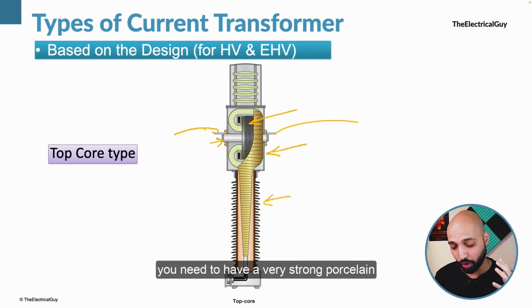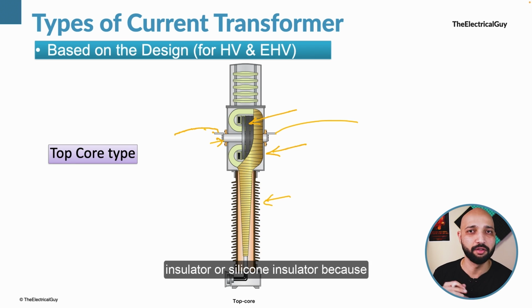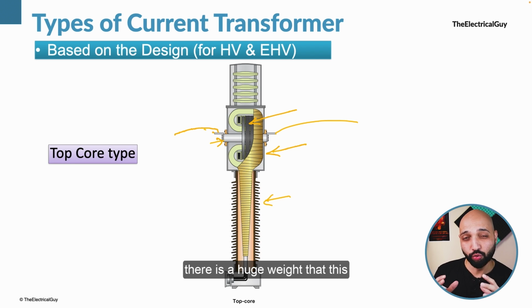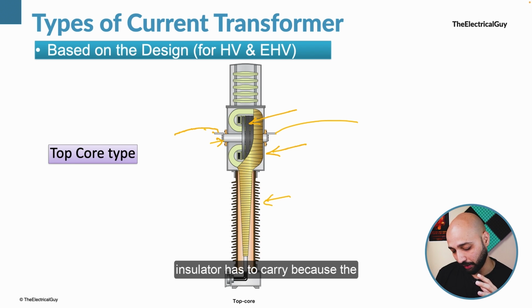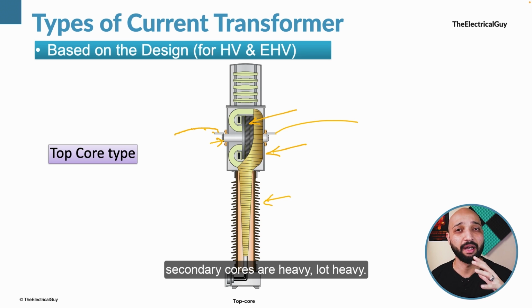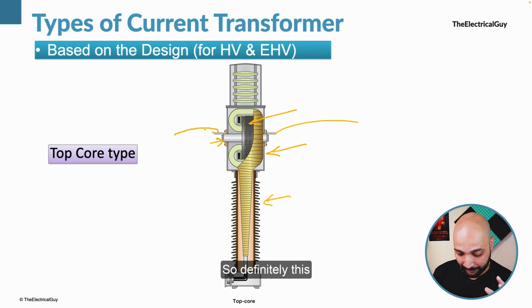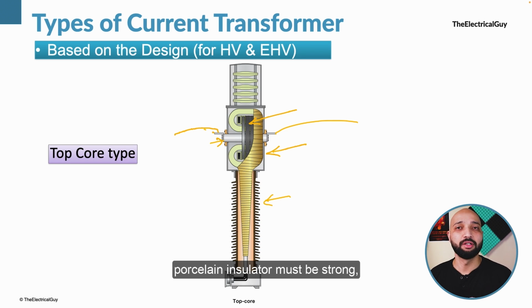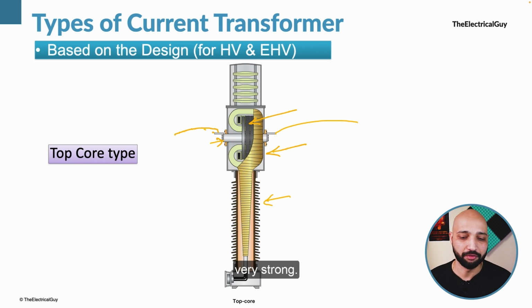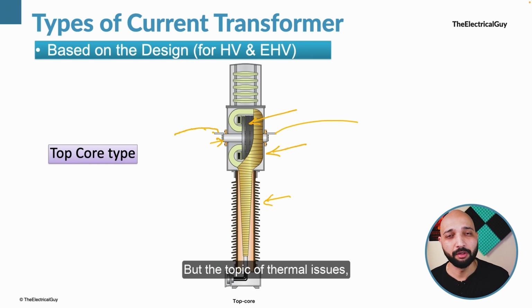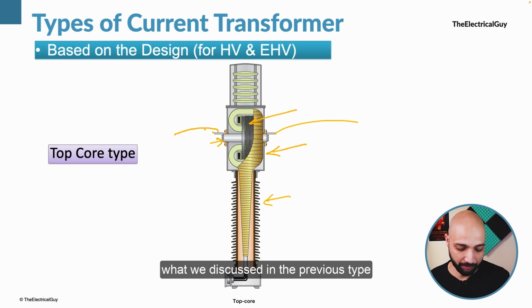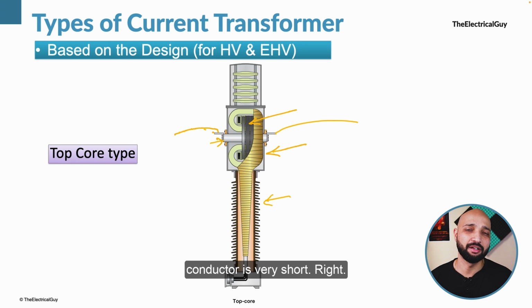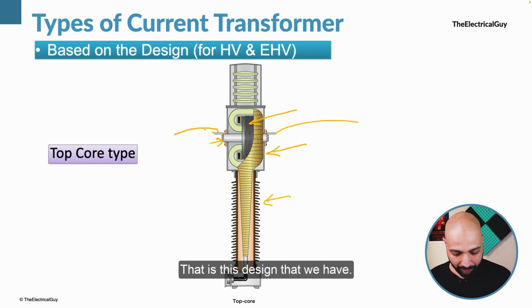But the catch here is that when you use a top core design, you need to have a very strong porcelain insulator or silicon insulator, because there is a huge weight that this insulator has to carry, because the secondary cores are heavy, a lot heavy. So definitely this porcelain insulator must be strong, very strong. But the thermal issues we discussed in the previous type are addressed here because the primary conductor is very short, right? So that is this design that we have.